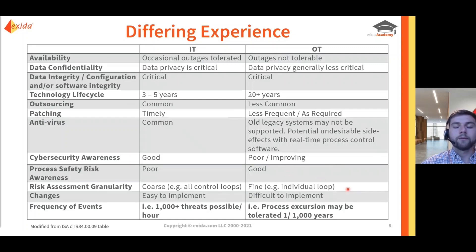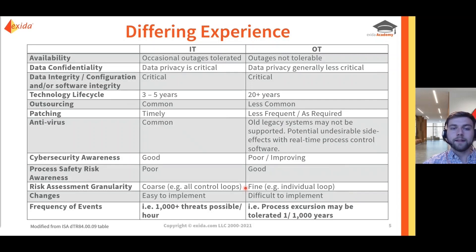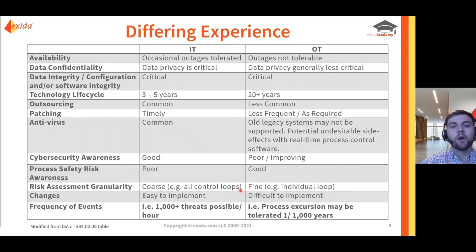We can also think about the level of granularity in risk assessments. When an OT cybersecurity risk assessment is done, they're really trying to understand the impact at an individual loop level — understanding the most critical parts of the system and what process excursion could be caused by an attack. An IT risk assessment would typically take a much coarser view and look at the OT system as one area, covering all control loops together, which may miss scenarios that would be identified at a finer level of detail.